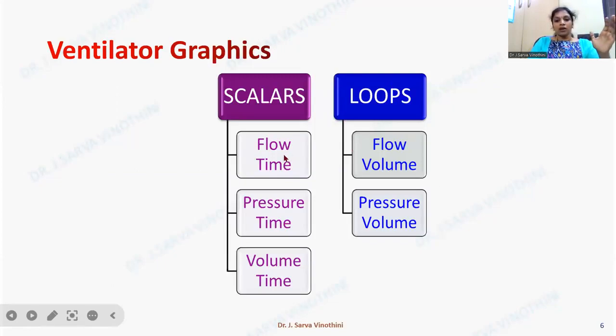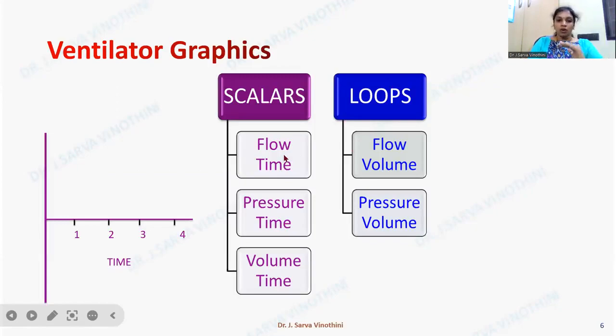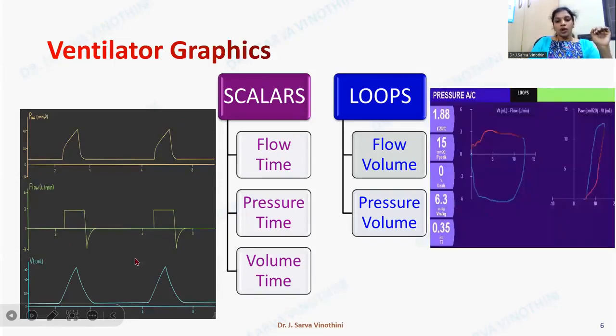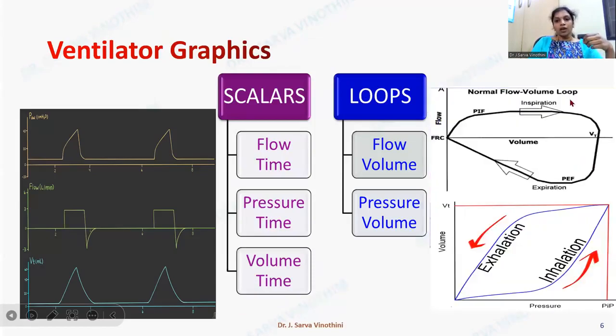Ventilator graphics can either be a scalar or a loop. A scalar means a single parameter is plotted over time — so it could be flow over time, pressure over time, or volume over time. A loop is where two scalars are plotted against each other — such as flow versus volume or pressure versus volume. It is called a loop because it ends at the same point where it begins.